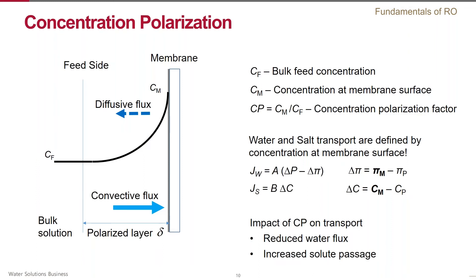The highest salt concentration Cm occurs at the surface of the membrane. Concentration polarization has a negative effect on RO membrane performance: it increases the osmotic pressure delta pi m within the boundary layer, effectively reducing the driving force for water through the membrane. Secondly, the higher concentration of solutes on the membrane surface Cm compared to the bulk leads to higher passage of solutes.